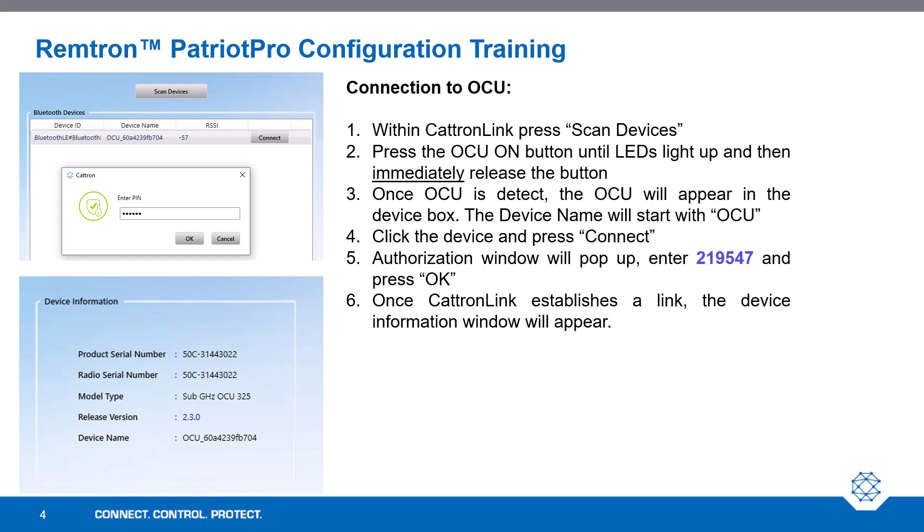After restarting the CattronLink program, within CattronLink, press Scan Devices. After that, press the OCU on button until all LEDs light up and then immediately release the button. Once the OCU is detected, it will appear in the device box. The device name will start with OCU. Click the device and press Connect. An authorization window will pop up. In that window, enter 219547 and press OK. Once CattronLink establishes a link, the device information will appear.